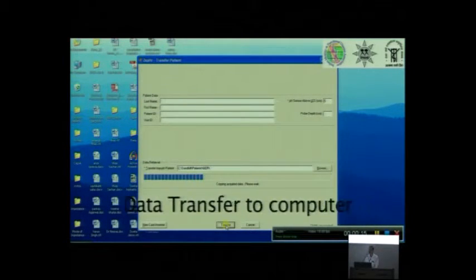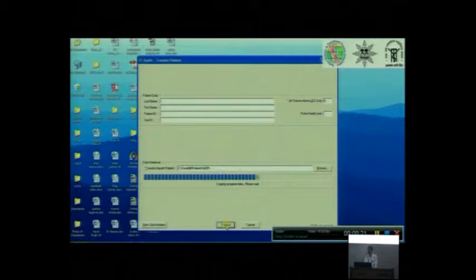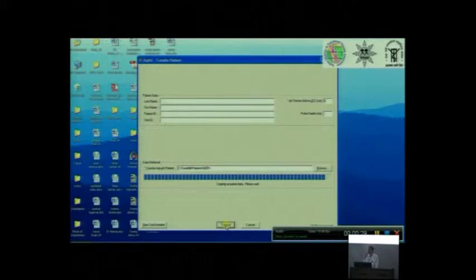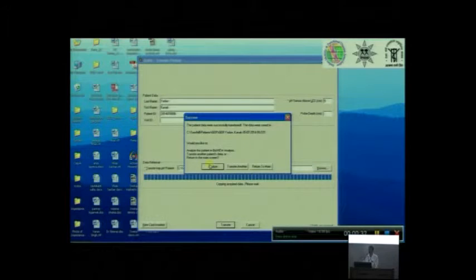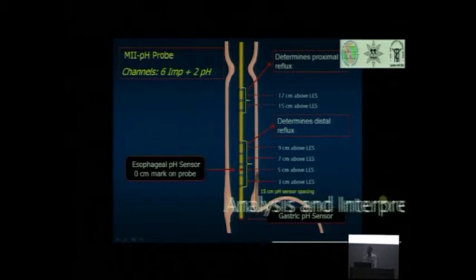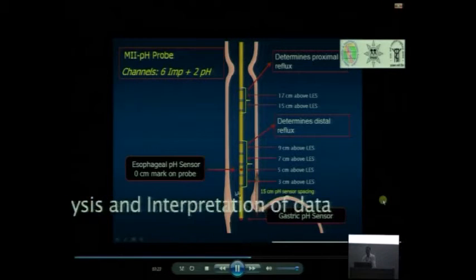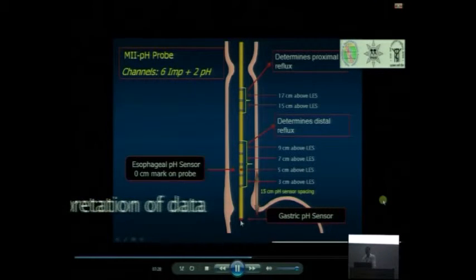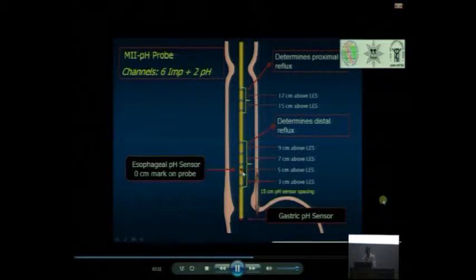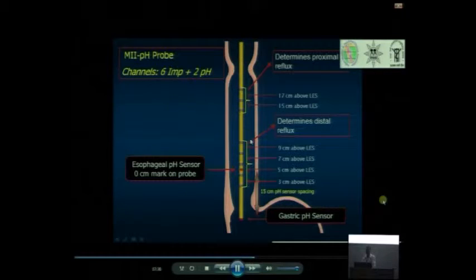Now you download the data. What you do is connect back to the computer the flash drive, and then you say download the data or transfer the data. Look at this, this is a transfer key. The moment you click, it will transfer all the data that we acquired during the pH metric, and then once you have transferred, go to analyze. This is our probe where you have two acid measuring probes or pH probes. This is the gastric pH sensor, and this is the esophageal pH sensor, and these are the impedance probes.